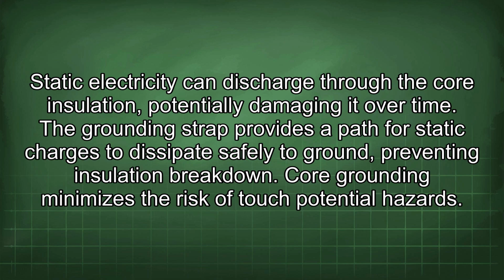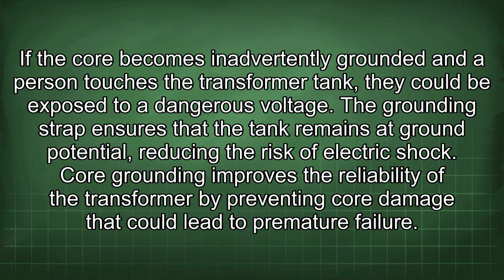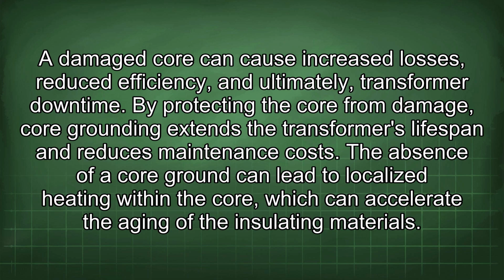Core grounding minimizes the risk of touch potential hazards. If the core becomes inadvertently grounded and a person touches the transformer tank, they could be exposed to a dangerous voltage. The grounding strap ensures that the tank remains at ground potential, reducing the risk of electric shock. Core grounding improves the reliability of the transformer by preventing core damage that could lead to premature failure. A damaged core can cause increased losses, reduced efficiency, and ultimately transformer downtime. By protecting the core from damage, core grounding extends the transformer's lifespan and reduces maintenance costs.